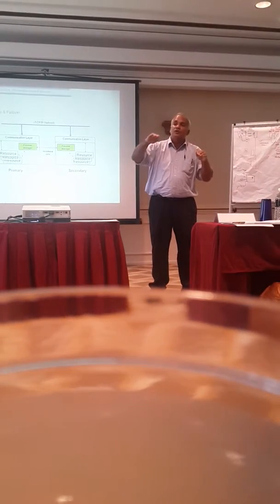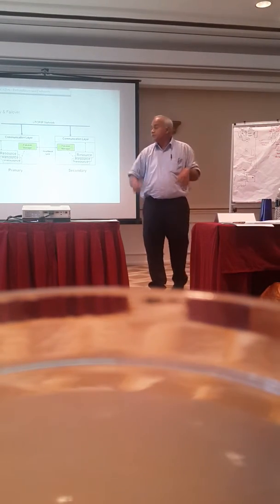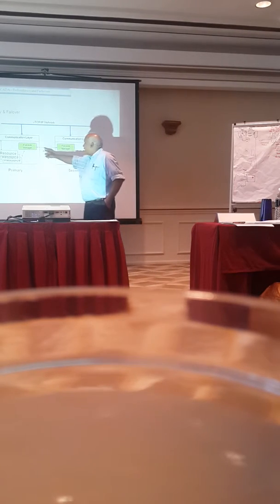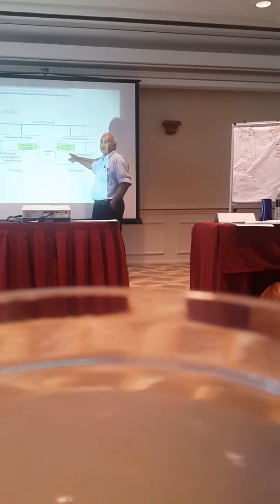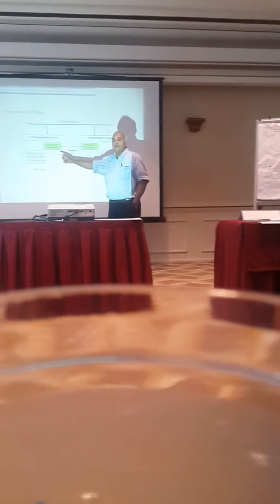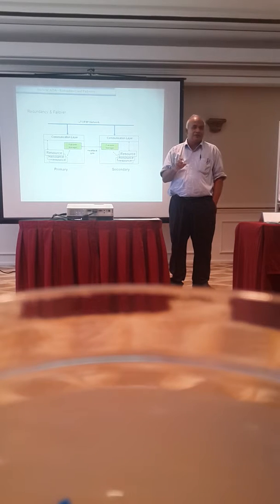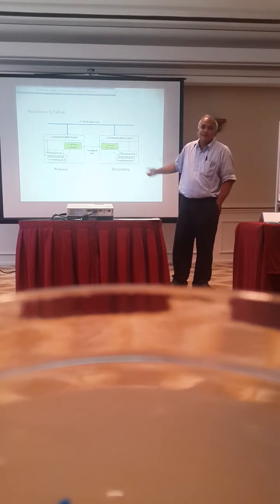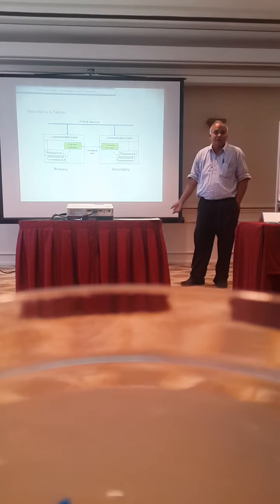Redundancy works like this: if you have the main controller and the secondary controller, both controllers operate, both listen and get inputs, but only one controller takes action - that is known as the primary controller. There is a wire connected between that controller and the secondary one. The secondary controller listens to the primary controller, like listening to a heartbeat - tuk tuk tuk tuk. When the heart stops, this one takes over automatically. Most controllers do that.